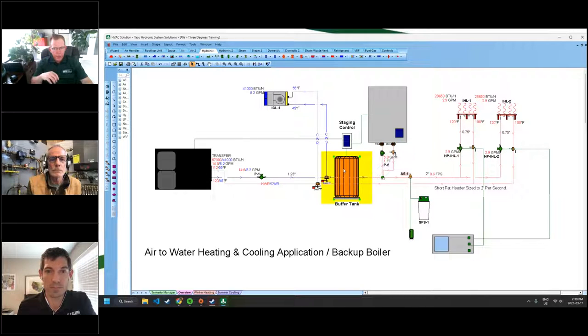I know that this tank is going to be at a certain set point, and I know that all this boiler is doing is running when I need it. This boiler actually does not come on when there isn't a heating call. So there's a lot more to the control logic. It's very simple, an off-the-shelf Tekmar control. There's nothing fancy about this. But that boiler will never come on unless there is a heating call, and this buffer tank does not have usable heat. And I like that.